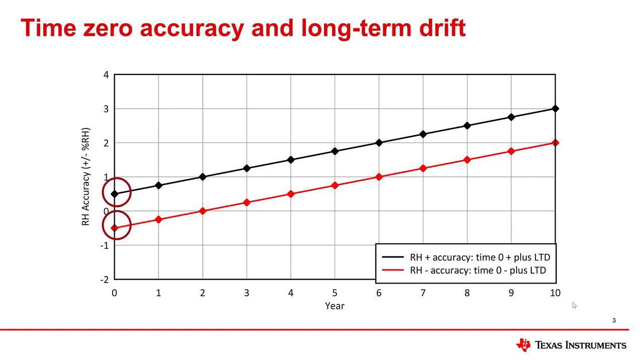The effect of long-term drift on a humidity sensor's accuracy is also seen in this graph, as the relative humidity accuracy deviates each year from the time zero value. As the sensor lifetime increases, the long-term drift begins to affect the initial time zero accuracy. Long-term drift is specified in datasheets as the percent relative humidity drift per year over the lifetime of the part. This lifetime drift assumes normal operating conditions and is not associated with drifts due to harsh environments or contaminants.